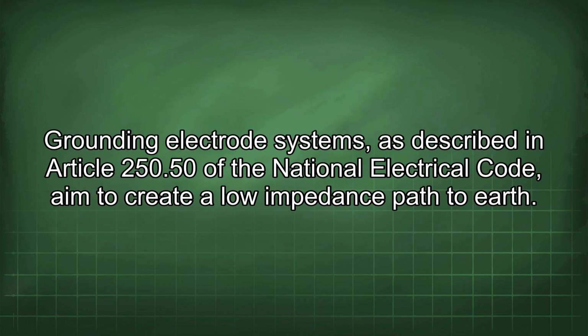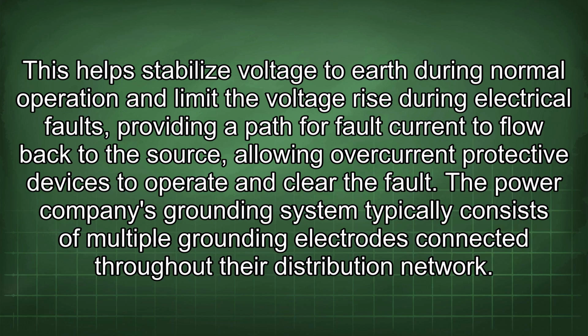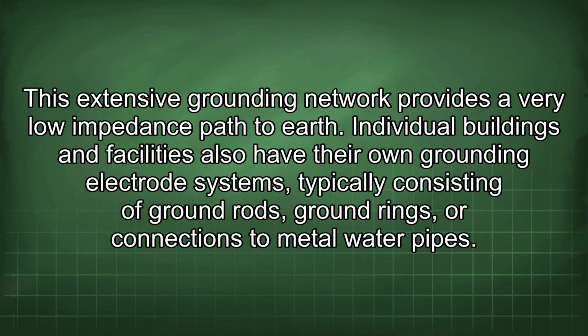Grounding electrode systems, as described in Article 250.50 of the National Electrical Code, aim to create a low-impedance path to Earth. This helps stabilize voltage to Earth during normal operation and limit the voltage rise during electrical faults, providing a path for fault current to flow back to the source, allowing overcurrent protective devices to operate and clear the fault. The power company's grounding system typically consists of multiple grounding electrodes connected throughout their distribution network. This extensive grounding network provides a very low impedance path to Earth.